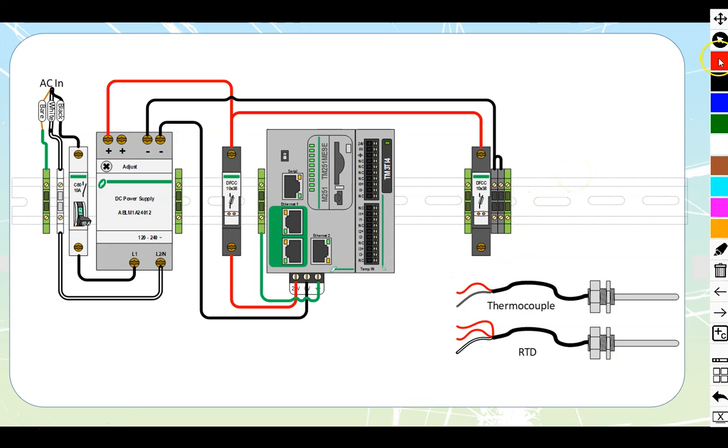Okay, let's start with the most important part, which is providing power to the card itself. So we're going to take in 24 volts, as well as a negative. And then we're also going to take in a ground from our closest ground like that. So this now provides power to this card so it can start sensing what we have for signal coming in there. Let's deal with the thermocouple first.